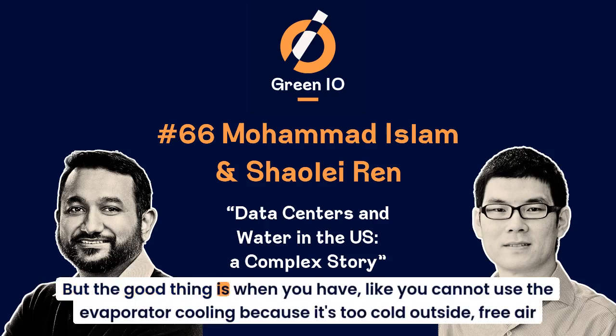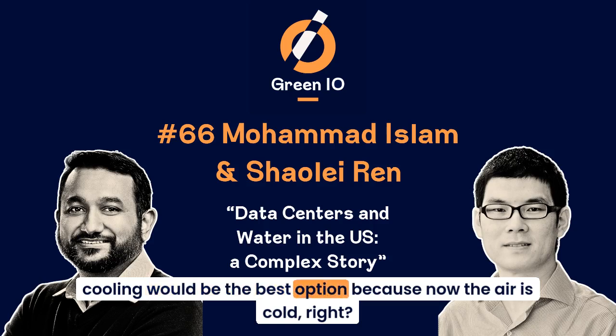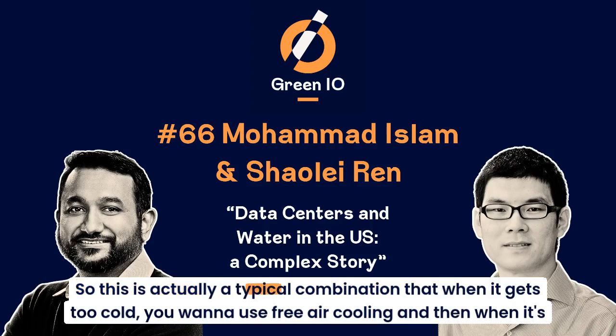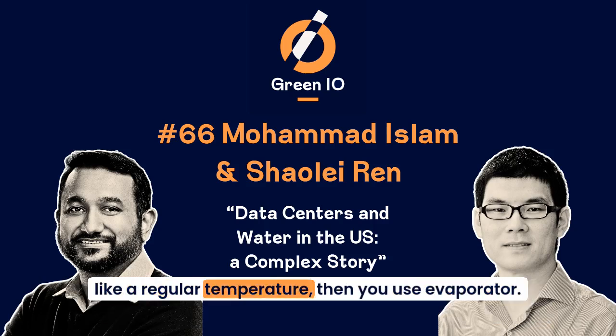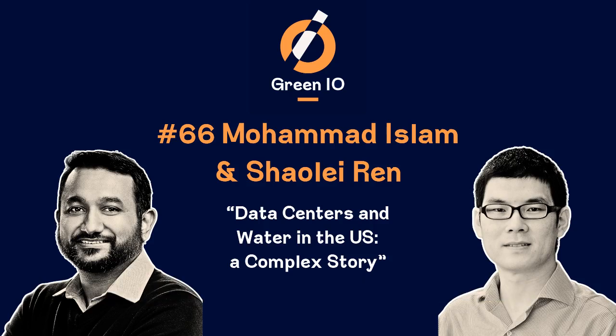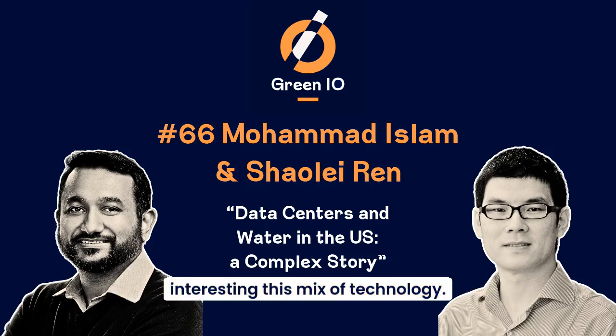But the good thing is, when you can't use evaporative cooling because it's too cold outside, free air cooling becomes the best option, because now the air itself is cold. So this is a typical combination: when it gets too cold, you use free air cooling, and when it's a regular temperature, you use evaporative cooling. It's an interesting mix of technology.